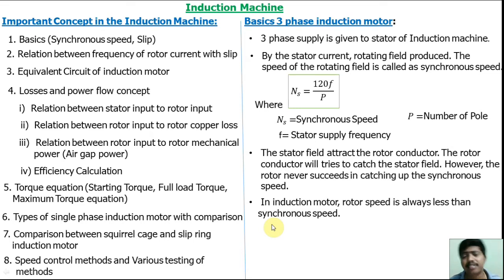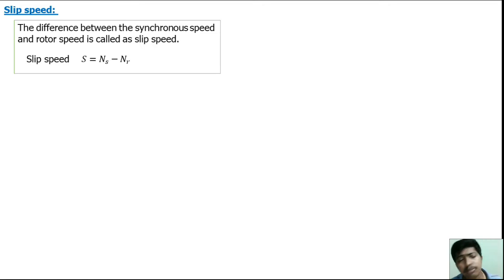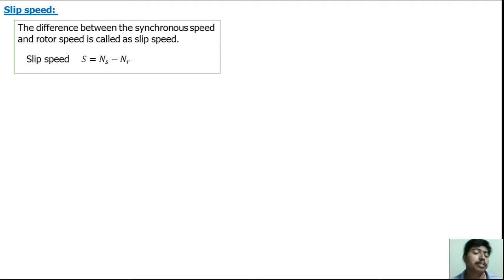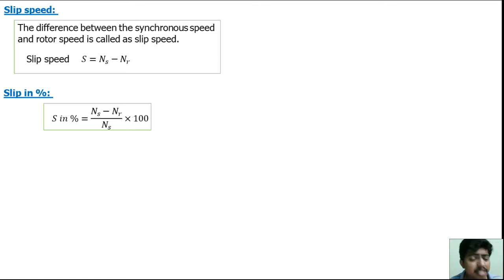If the rotor rotates faster than synchronous speed, the machine acts as an induction generator. Slip speed is defined as the difference between synchronous speed and rotor speed: slip speed = Ns − Nr. Slip in percentage is defined as the ratio of slip speed to synchronous speed: slip = (Ns − Nr) / Ns × 100. These are the basic concepts.